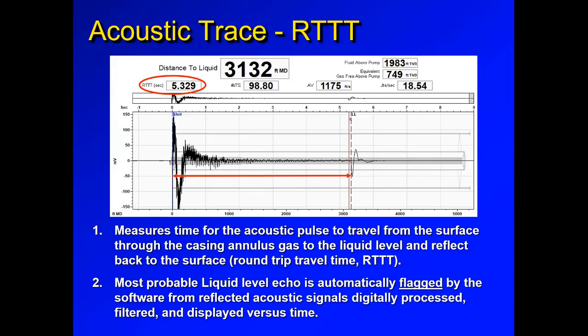Now, let's look at some real data. The acoustic trace will be represented on the screen, and we have the time to the liquid level, 5.329. That's coming from the average well example. Every time you install the TAM software, there is an example folder with a number of wells. One of those wells is the example well, and you can always pull it up and look at it. It has this acoustic liquid level reflection. So the software will select the liquid level and determine distance and time to the liquid, and with some information, we'll calculate the average joint length, and we'll go there for a second.